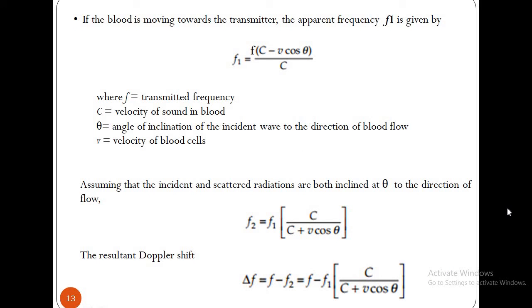If the blood is moving towards the transmitter, the apparent frequency F1 is given by F into (C minus V cos theta) divided by C, where F is the transmitted frequency, C is the velocity of sound in blood, theta is the angle of inclination of the incident wave to the direction of blood flow, and V is the velocity of blood cells. Assuming that the incident and scattered radiations are both inclined at angle theta to the direction of flow, then F2 is given by F1 into C divided by (C plus V cos theta).